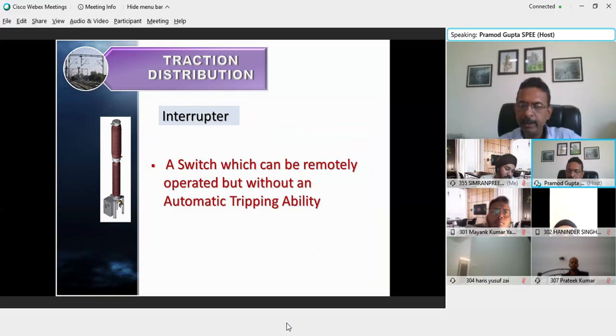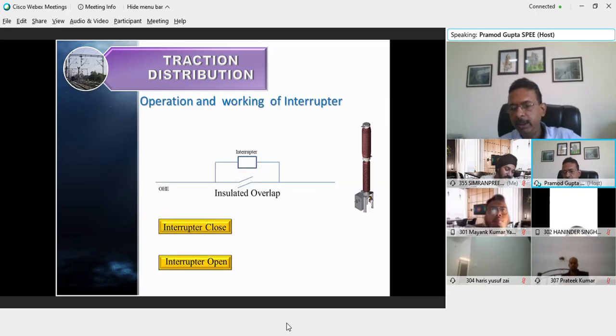The interrupter is a different switching device. It is a switch which can be remotely operated, but it does not have the ability to operate automatically, and it does not get tripped automatically on its own under faulty conditions. Now let us see how the interrupter works at the insulated overlap.